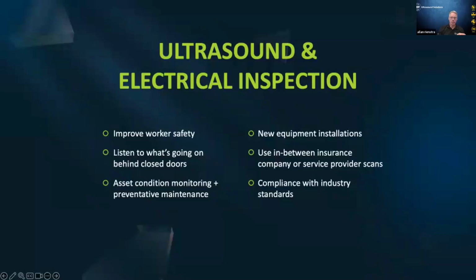Another advantage is its flexibility. It can be used in the intervals between infrared scans. If you don't have an in-house infrared thermography program, and you're outsourcing that either to an insurance company or a third party, they're not going to be on site doing those inspections. Sometimes some places don't do any infrared thermography. Some do it annually, some quarterly. In between those, having an ultrasound program and a qualified inspector that can come in and perform in between just fills the gaps and gives you a more complete view of the story.